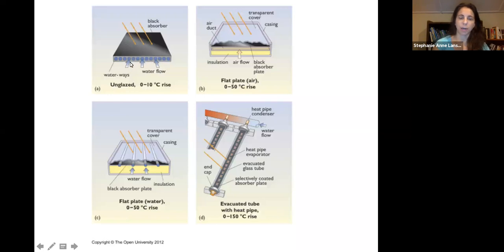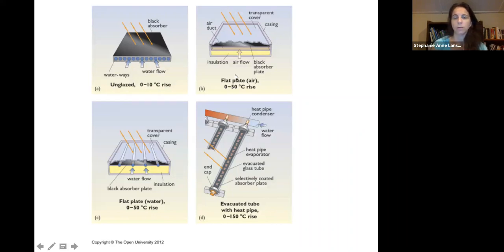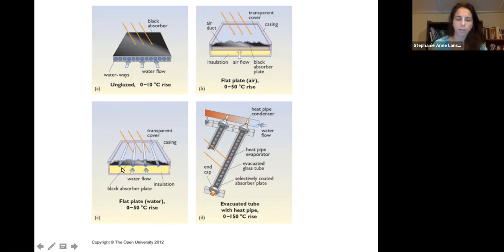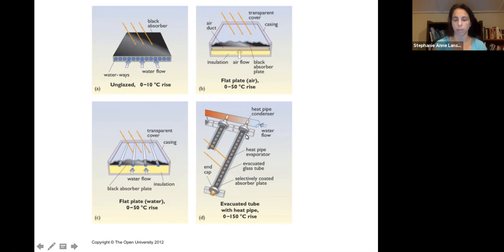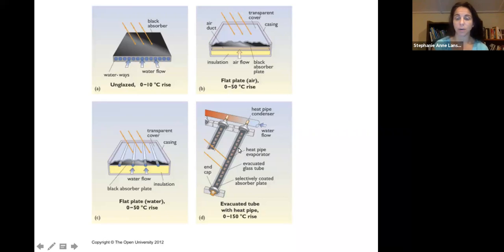An unglazed system simply has water flowing through a black absorber, giving a temperature rise of roughly 0 to 10 degrees Celsius. You can also have a flat plate with air flowing through, with that hot air used for heating inside the home. A flat plate with water or glycol is another option. Most systems today use evacuated tubes rather than flat plates, because evacuated tubes provide less heat loss and therefore greater energy gain.